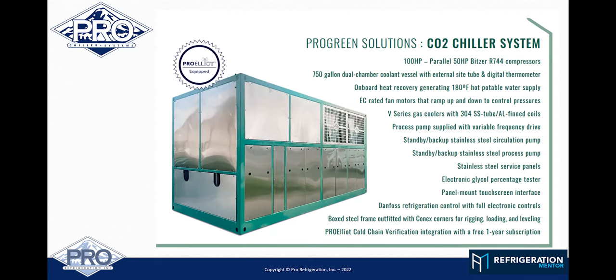We have process pumps, and everything's got backup pumps. Our process pump feeds the customer's process loop with coolant, and our circulation pump is our internal circulation pump that feeds our evaporator. Everything's standby and backup, so if there's a failure on a primary, it's easy for the customer to switch to the backup pump and get a service technician out to look at it.